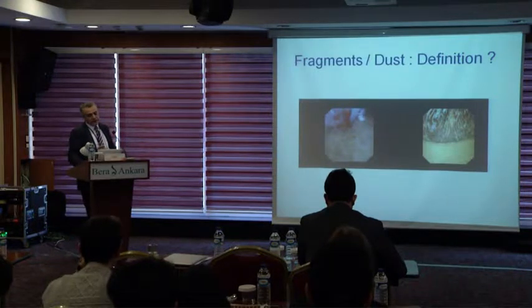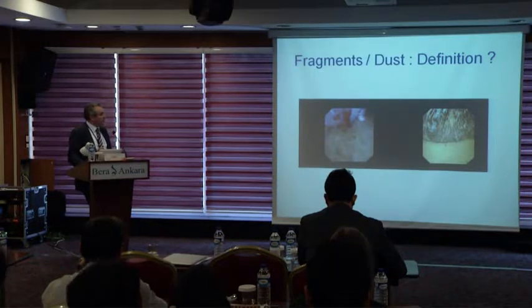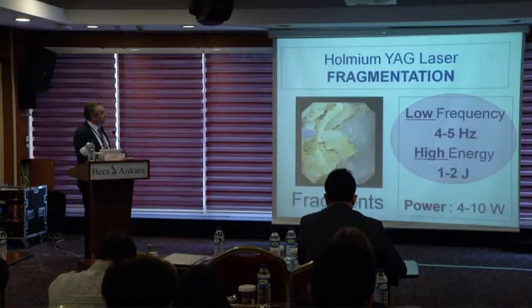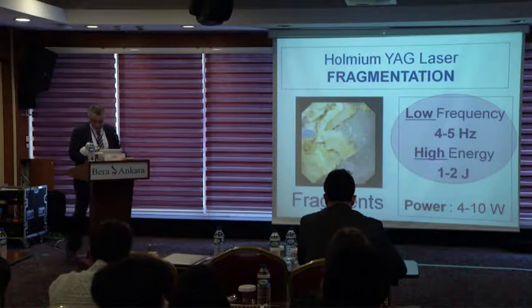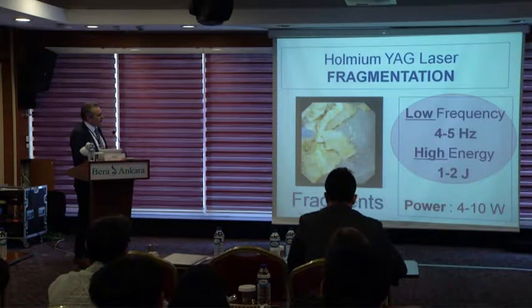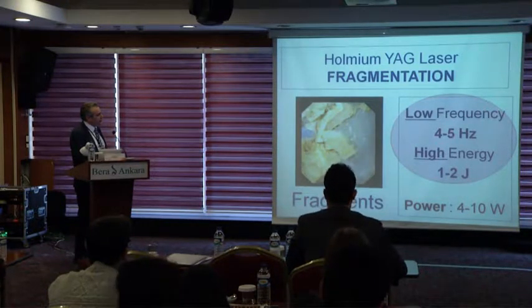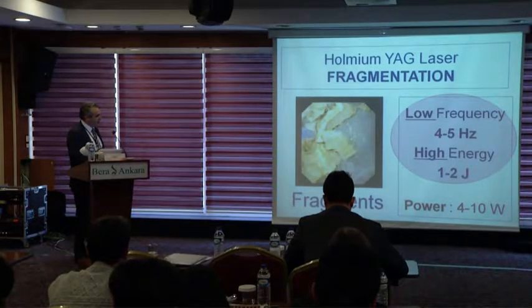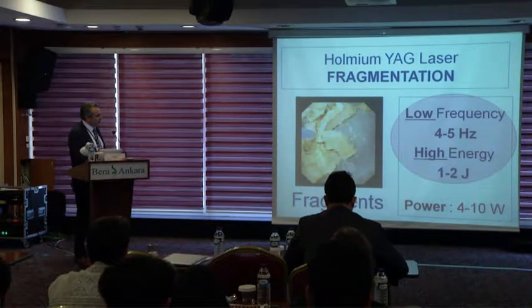Shall we do fragmentation or dusting? What is fragmentation or what is dusting in kidney stones? For fragmentation, the energy setting will be high, but the frequency will be low. 4 to 6 hertz is enough. The power setting will be 4 to 10 watts.